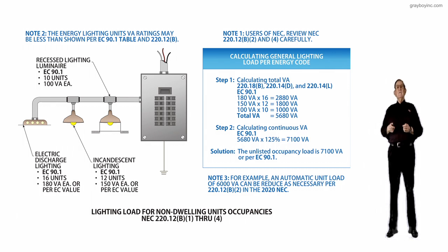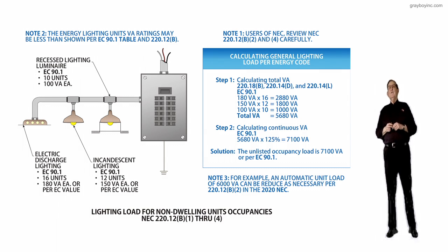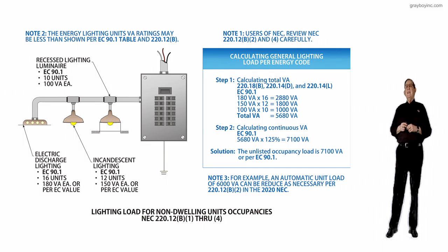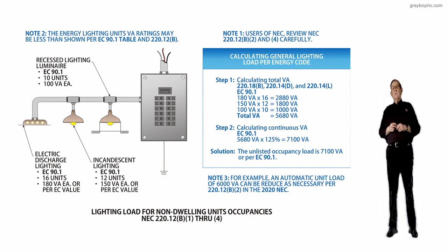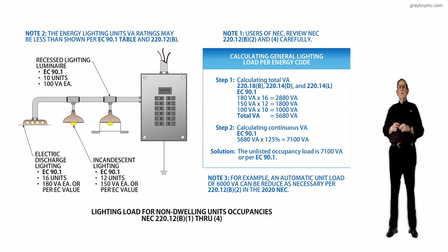Now notice this is an office building when you review the information to the left of the occupancy. It's 15,000 square feet of halls and various things. It's 277 volt and 3-phase. Now, notice that we review our Table 220.12 and Table 220.42 for new VA per square foot values to see what can be used and if we can apply demand to the lighting load or not.